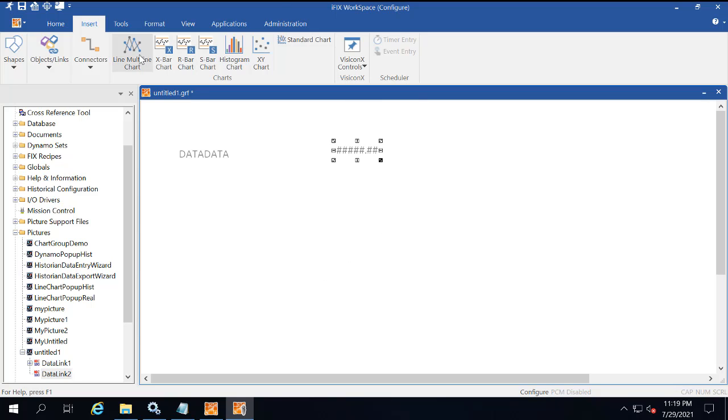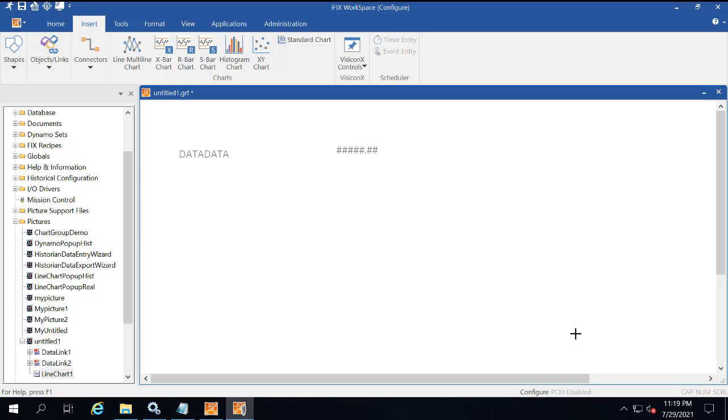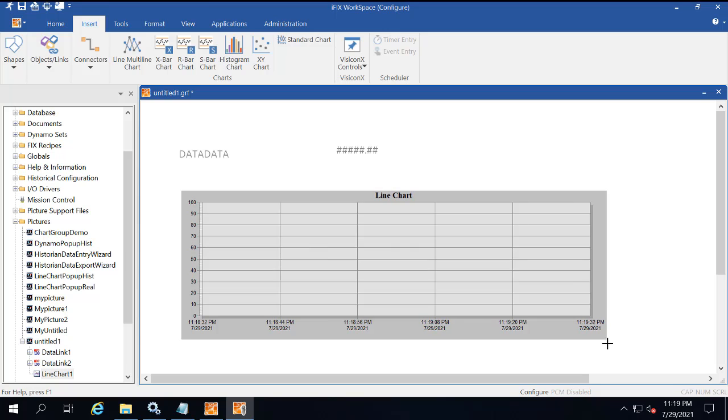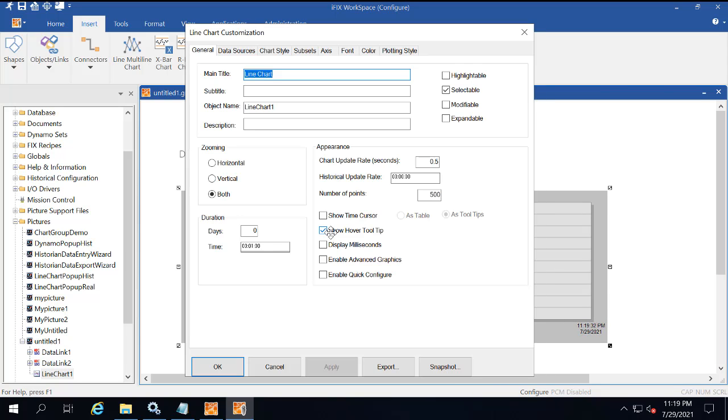Next, we're going to insert a line multi-line chart. With your picture open in the iFix workspace, click the Insert tab. Select the line multi-line chart. The cursor is going to turn into a crosshair. Draw a rectangle where you want the chart to appear in the picture. Now double click the chart to view the settings. On the General tab, select the duration time to 10 minutes.